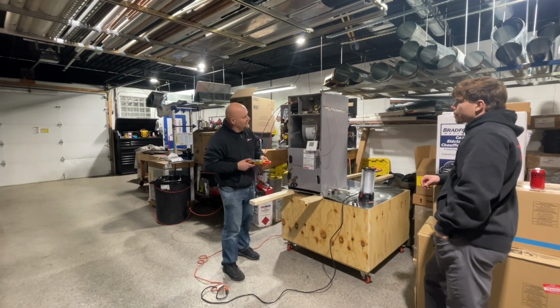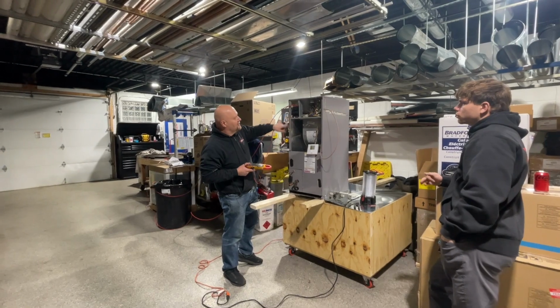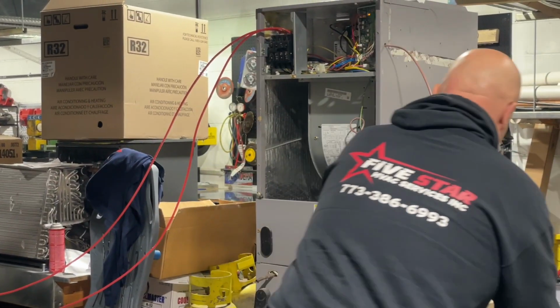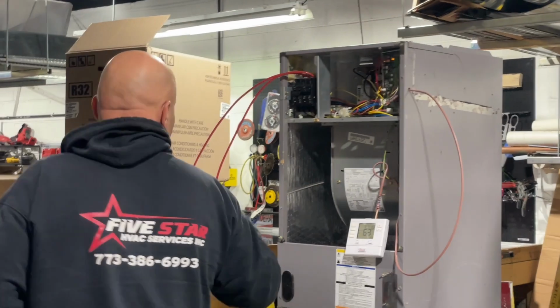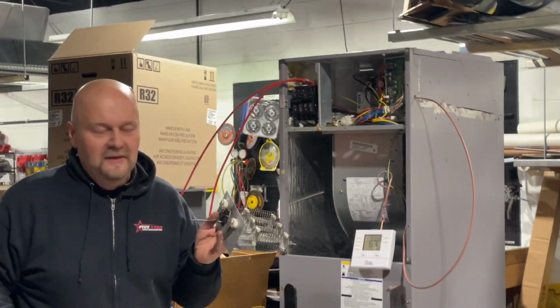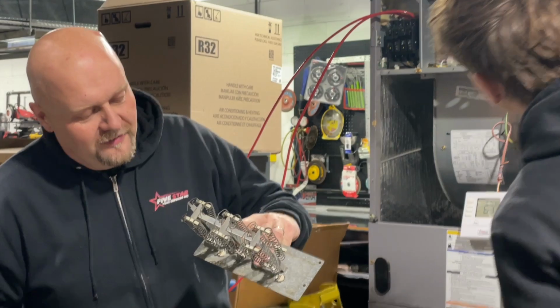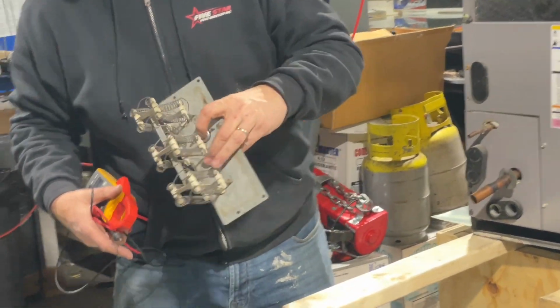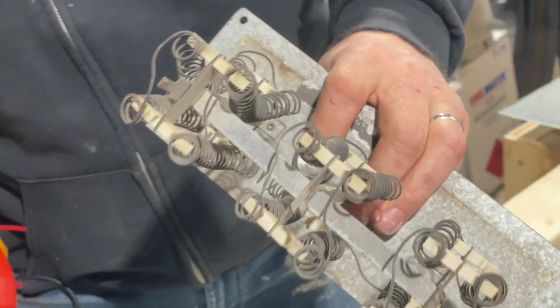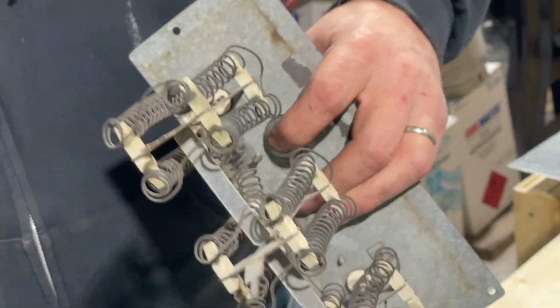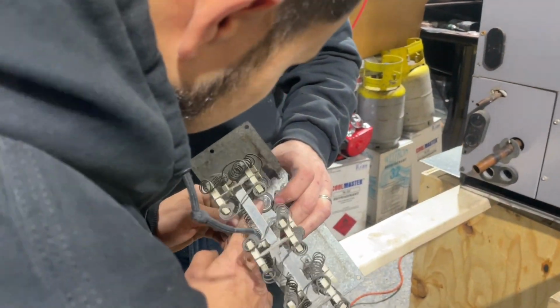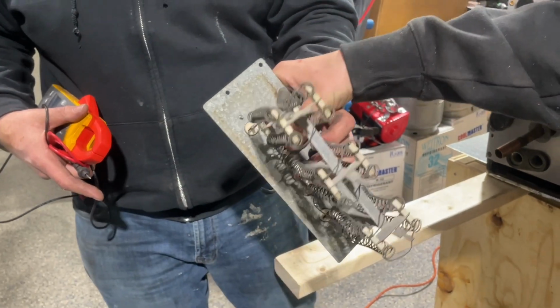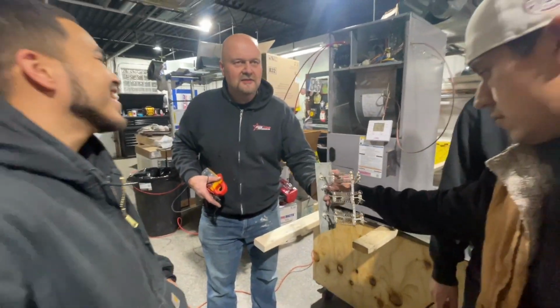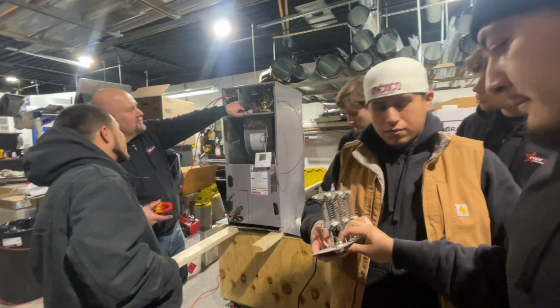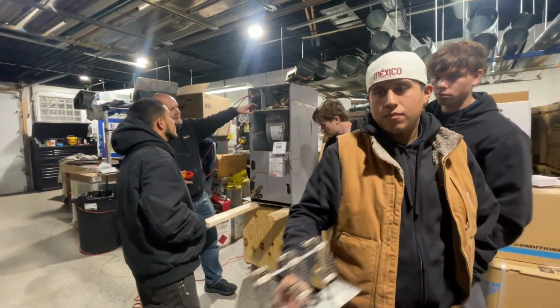So, good. One more thing to remember, two things that you're going to look for is always a thermal disc, right? If you look inside there, you're going to see three separate thermal discs, right? Each one of them is going to be like this, and each one in the back of it has this snap disc. If you want, just come feel it. This snap disc literally pops in and out. You can hear it. So when it overheats, it basically pops itself in, and then see, feel that, right? You see that? You actually feel it. So that's what happens. It's good. Pass this thing around, brothers. So those, you see, they're sitting there inside the airflow, and the back is where it reads the temperature.